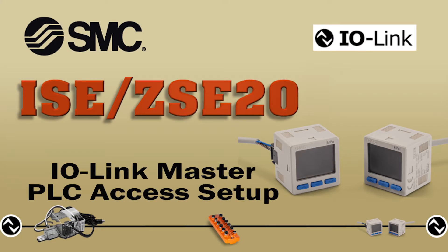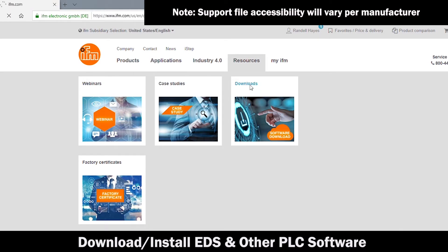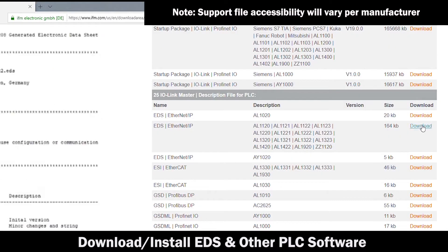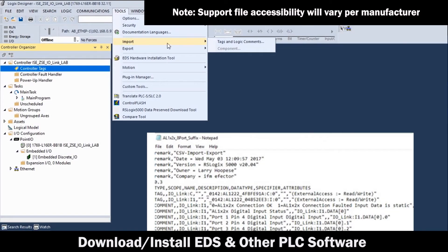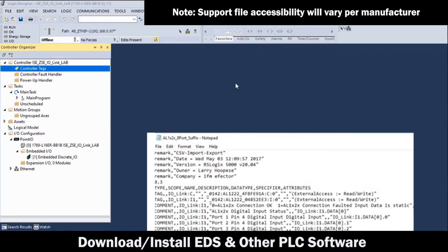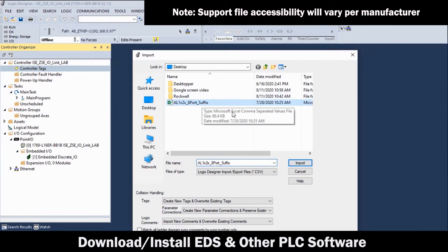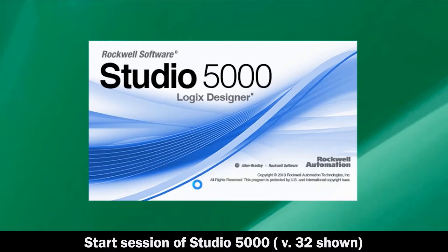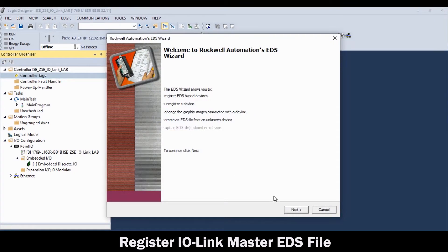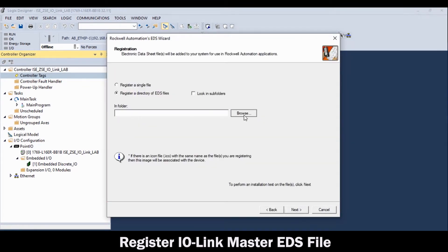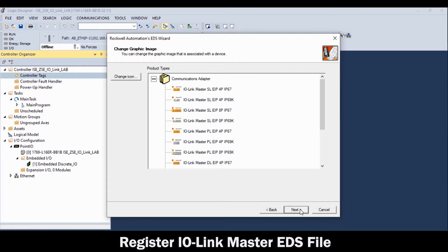Now, let's set up the IO-Link master for the PLC. Download the EDS file from the IO-Link master manufacturer. Also, download all necessary files for PLC access support. Now, with the IO-Link network running, start a session of Studio 5000. Then, select and add the IO-Link master EDS file and click Finish.